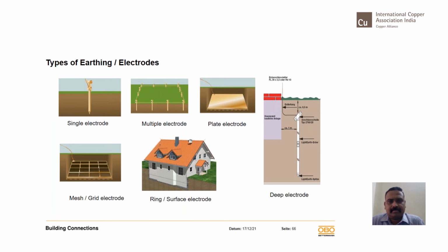Now, in a location where going deeper is not possible, the soil is not cooperative, then you'll have to have multiple rods and connect them together. Even in places where this is absolutely not possible, you have a rock and you can only dig up to 1 meter below, then possibly you can try a plate earthing. And especially in areas of substation, where you can find the mesh system, like horizontal conductors and vertical conductors connected together. This is something very critical, where in substations resistance alone does not matter. You need to bring down step potential, touch potential, and ground potential rise in control, for which you need to have a meshed system with a horizontal conductor and vertical conductor running in, and that will help you in reducing the resistance, that will help you in reducing the step touch potential and GPR.